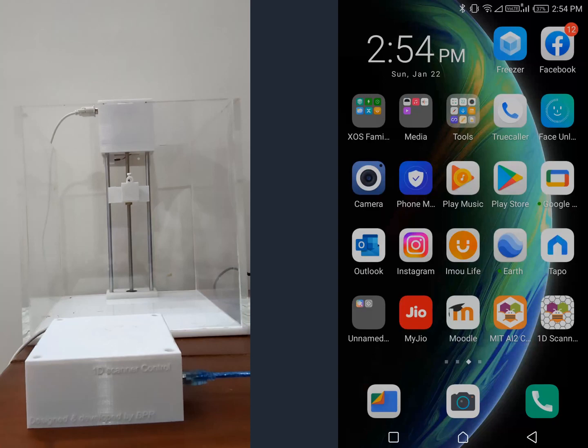What you see on the left is the 1D water phantom. It has a perspex tank, which I bought, and a system that can move the ion chamber within the water phantom. This block on the top has an assembly in which the stepper motor is fixed, and at the bottom you see a tiny box which holds a hall effect sensor.